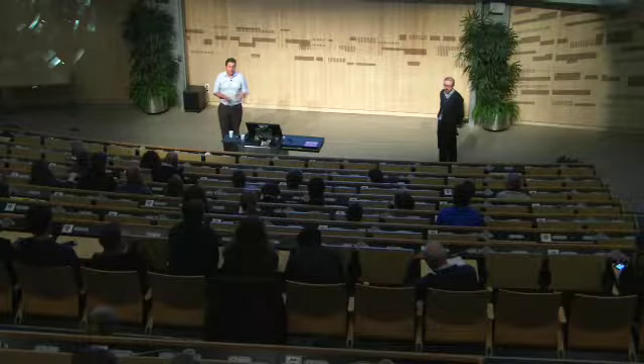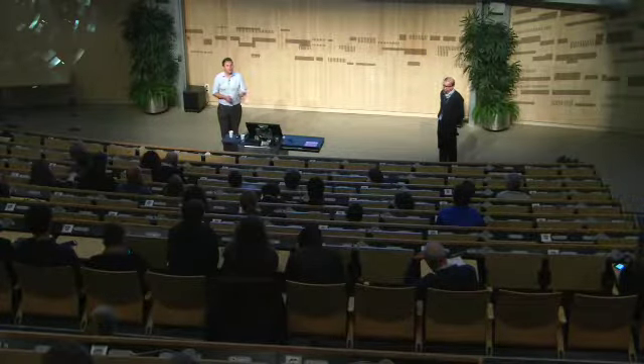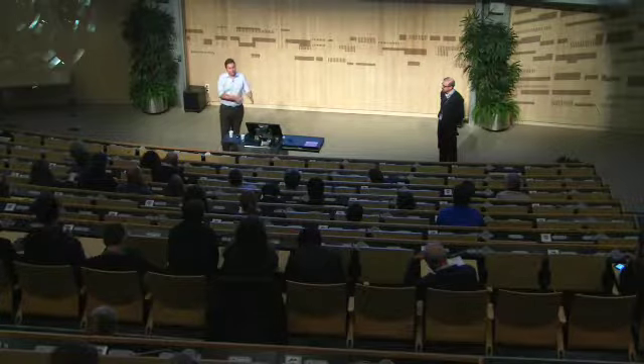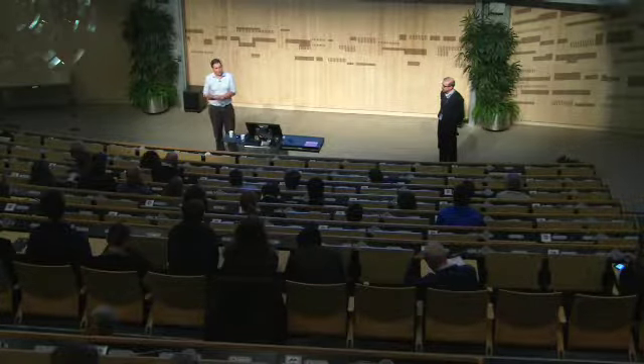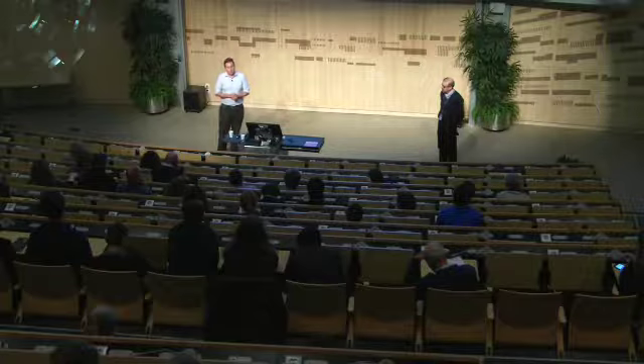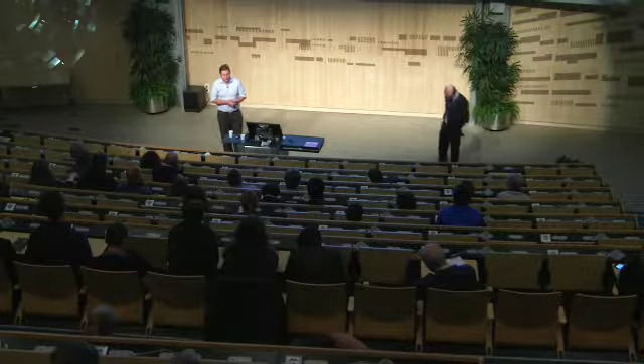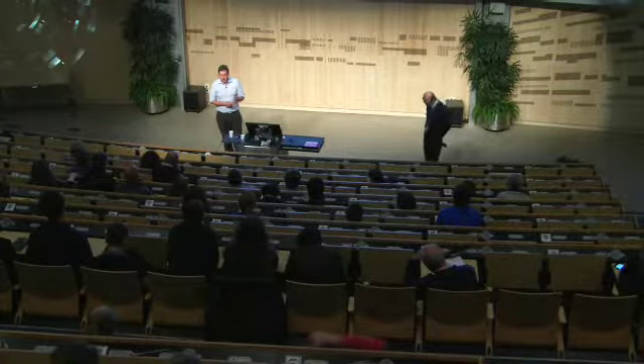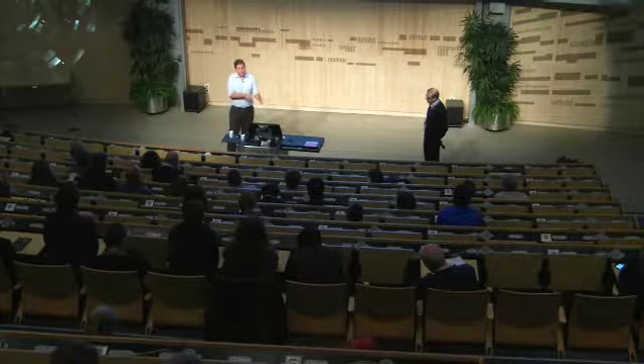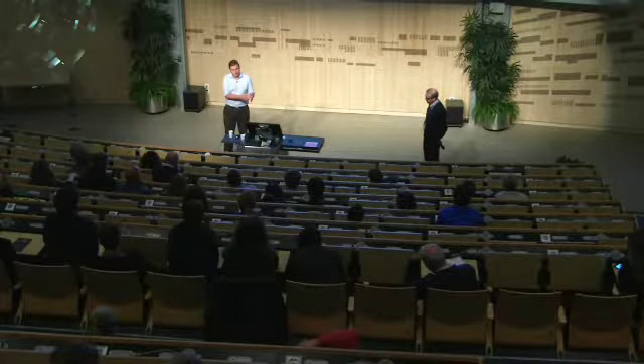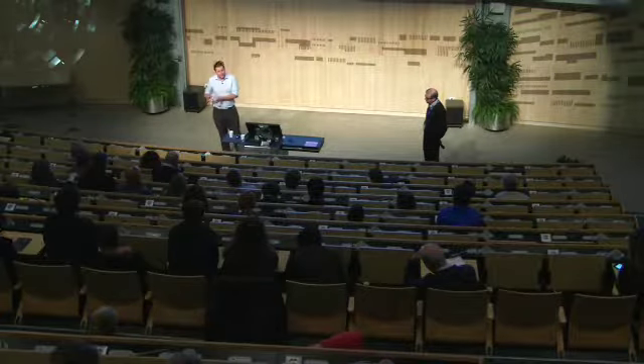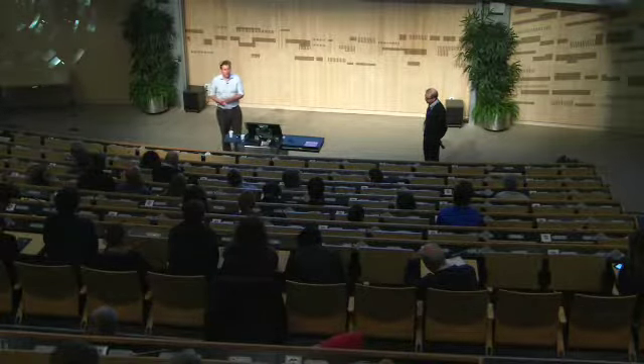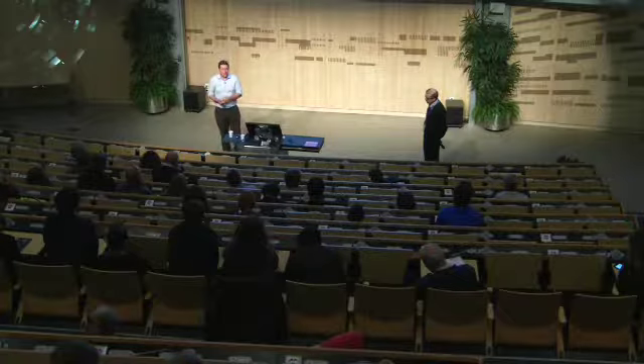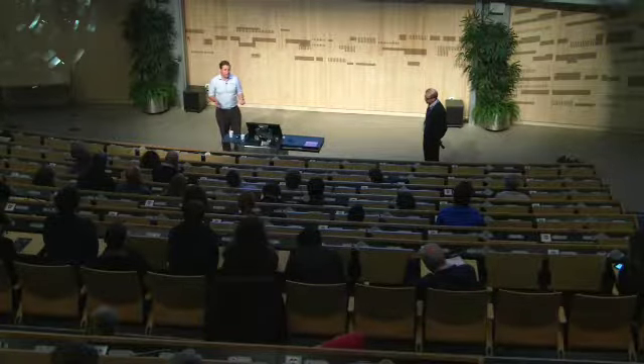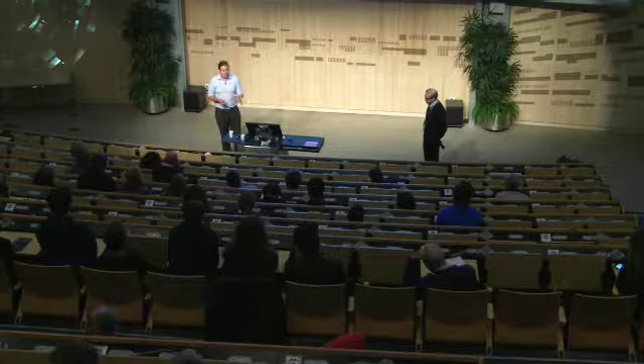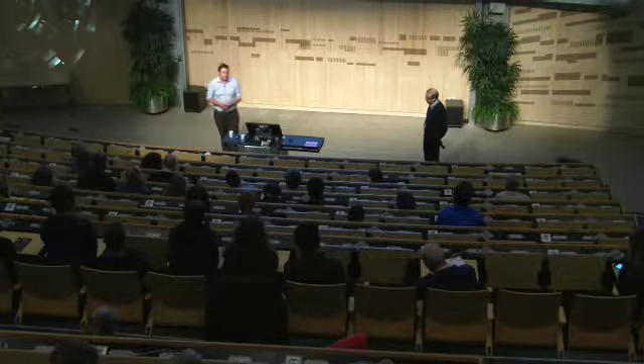And in fact, you know, the obvious thing is it shouldn't be a two-step. It shouldn't be spatial reconstruction and material reconstruction. It should be done as one step. We actually did some work with Erlangen University about 10 years ago where we did it the other way around. We did the material reconstruction in the projection space and the sinogram space, and then did the spatial reconstruction second, and we found that introduced too much noise. But the obvious physics answer is it's not step one, step two, or two then one. It's one problem, and it needs to be treated as one problem.